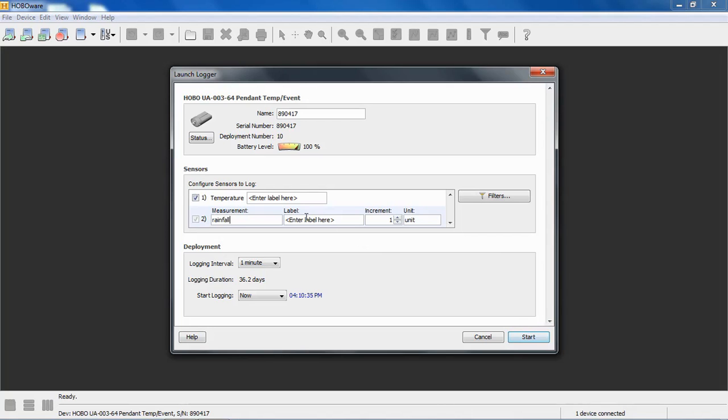You can give it another label. You have a measurement, a label, and then this is where you can put in your increment. So the RG3, the U.S. version of the rain gauge, each tip represents 1 one-hundredth of an inch of rain. Here, you can put in inches.